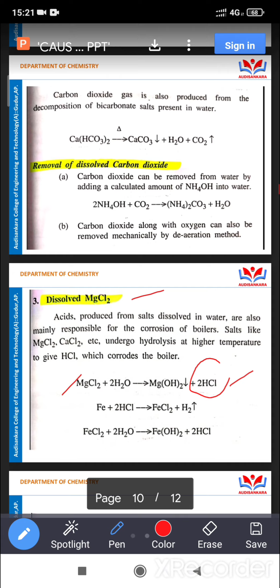Acids produced from the salts dissolved in water are also mainly responsible for the corrosiveness of boilers. Salts like MgCl2, CaCl2, etc. undergo hydrolysis at high temperature to give HCl, which corrodes the boilers. MgCl2 + 2H2O gives rise to Mg(OH)2 + 2HCl. This acid again reacts with the boiler Fe: FeCl2 is developed and H2 is released. This FeCl2 reacts with water to give Fe(OH)2 + 2HCl. Ferrous hydroxide is developed, one type of corrosion product.